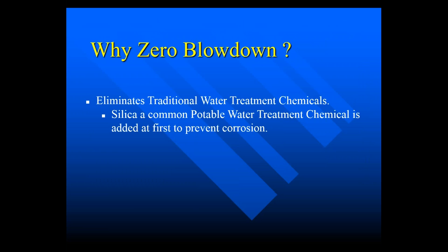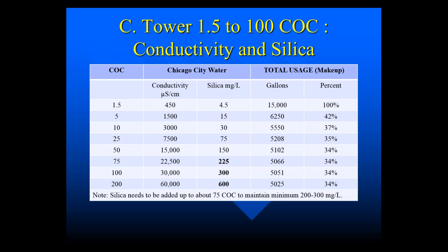Zero blowdown eliminates traditional water treatment chemicals and silica is a common potable water treatment. It is added initially when transferring from a traditional treatment program to the zero blowdown program. Silica is added to prevent corrosion. In Chicago city water, there's about 3 milligrams per liter silica, so to get to the recommended level of 200 to 300 mg/L silica just by cycling up, you don't get there until you're at 75 cycles of concentration — so in the lower range you'd have to add additional silica to reach recommended levels.